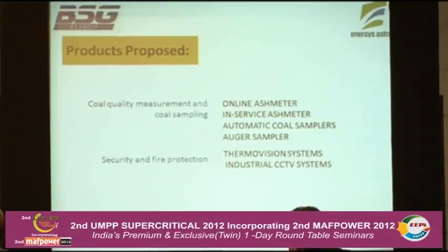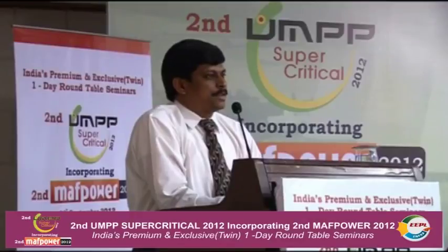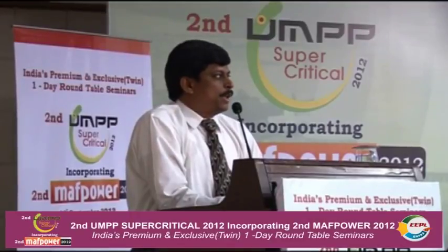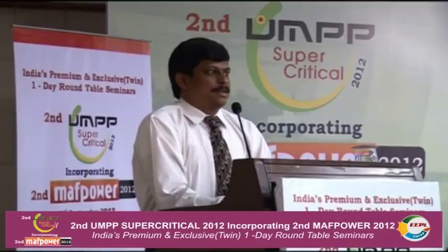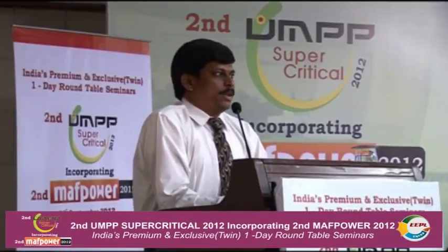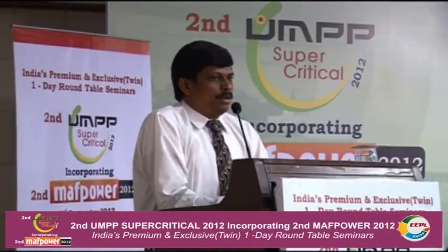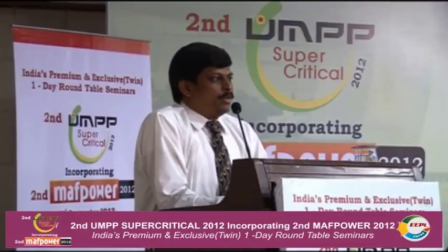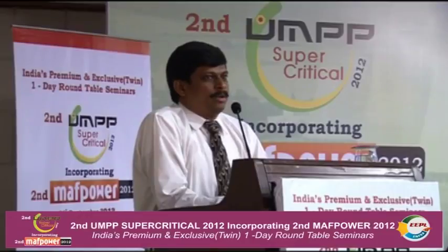The required ash content for effective combustion in the boiler, giving real output efficiency, is 13 to 17%. To achieve this, most power plants today do coal homogenization, mixing Indian coal and imported coal in a ratio of 70% Indian to 30% imported.